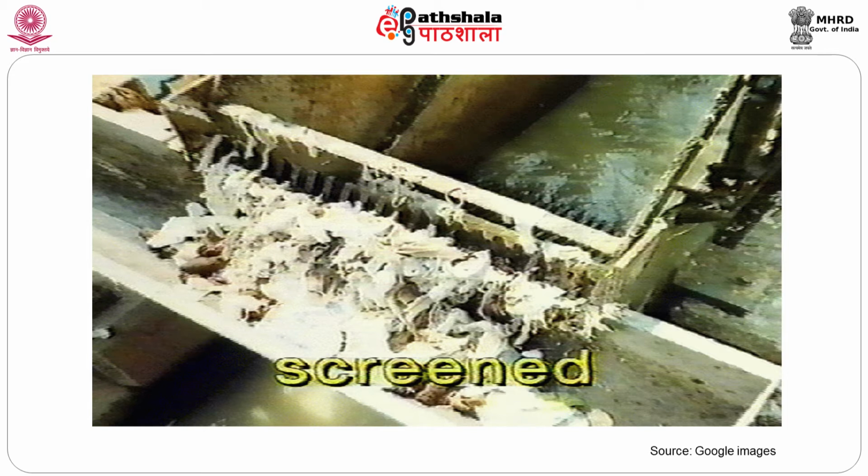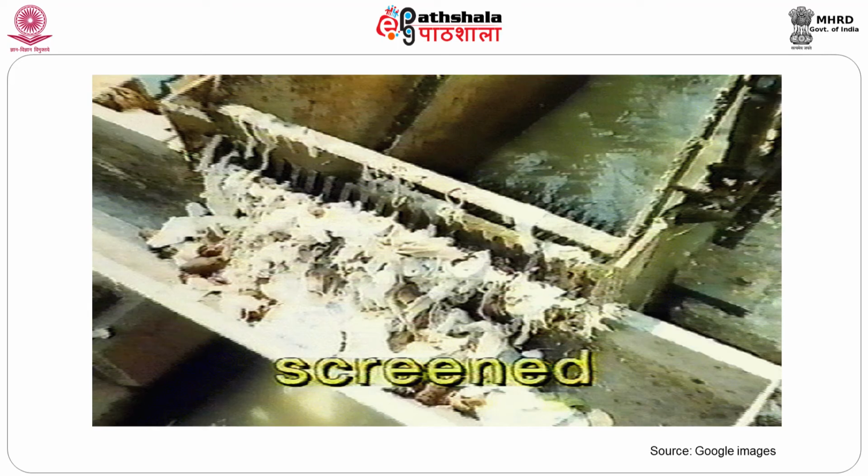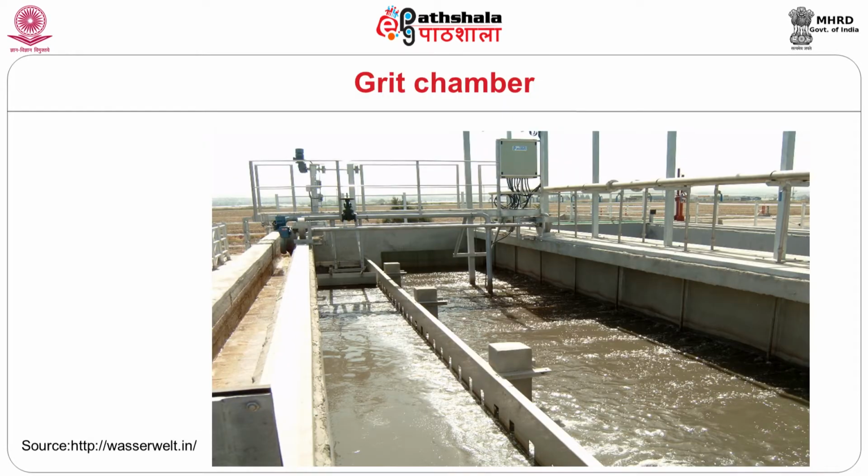While designing the configuration of the screening facility, the permitted head loss at the time of commissioning of the screen is 15 centimeter. Once 50% of the openings are covered by floating matter, we can permit the screen to allow 30 centimeter head loss. This is a grit chamber.